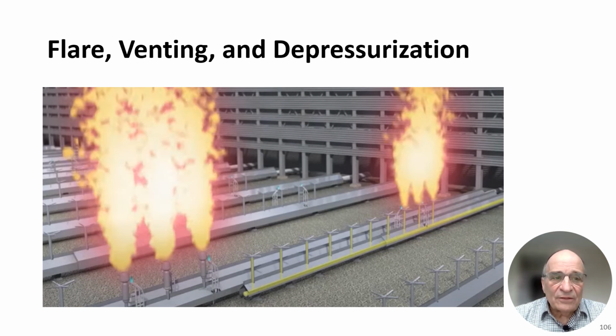Relieving pressure in a plant or venting or flaring is very important. Venting is often performed, certainly at the relief valves on the top of the tank. But if you need to vent gas from the plant process, you typically would heat that gas up to a temperature greater, typically warmer than minus 50 degrees. Because remember, gas becomes buoyant at minus 150 degrees. Colder than that, it's heavier than air. So you don't want to vent gas and have it come back down to ground level. You want it to dissipate into the air.